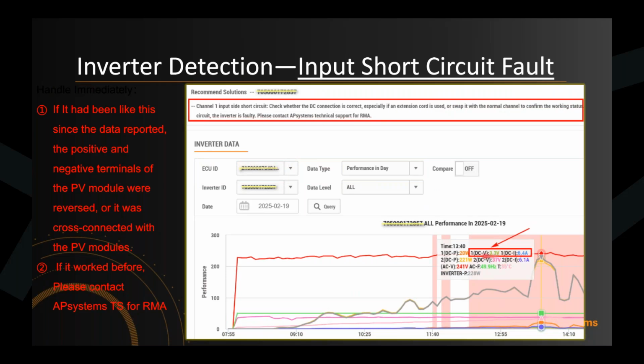But if it has always reported this way, we've seen this result from either the terminals of the modules being reversed, or a cross connection where one whip from one module is connected to another whip of another module on the same channel. That can also cause this sort of short circuit issue. So to summarize, if it's always functioned like this, the terminals may have been swapped or cross connected. But if it worked normally before, give us a call and we can evaluate whether it needs a replacement.